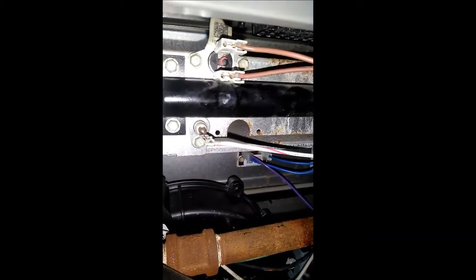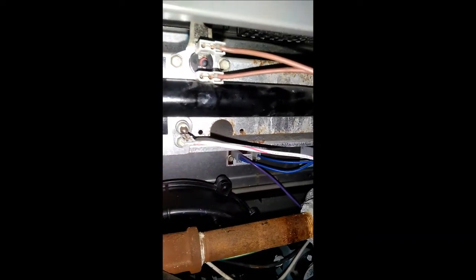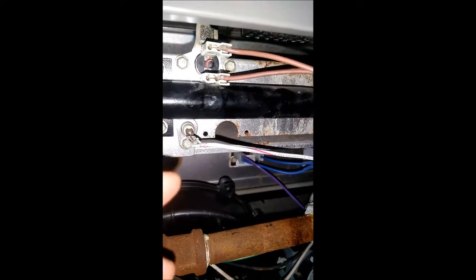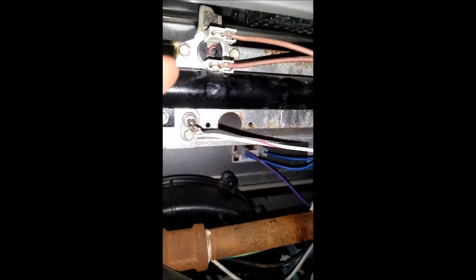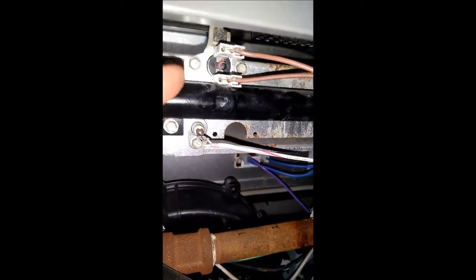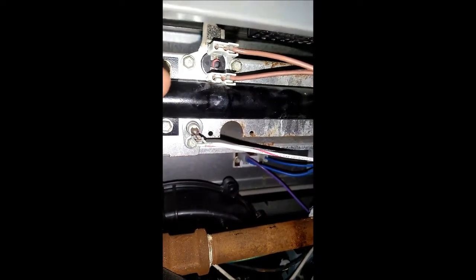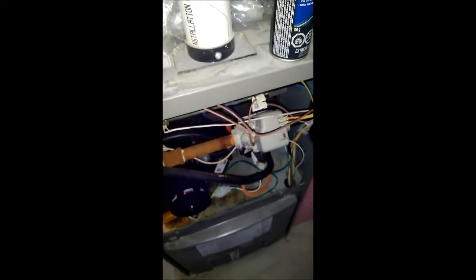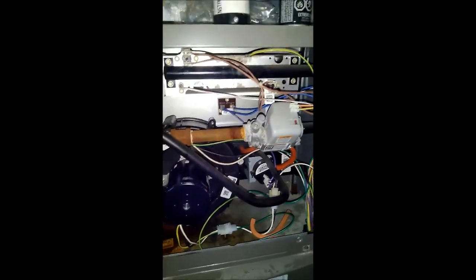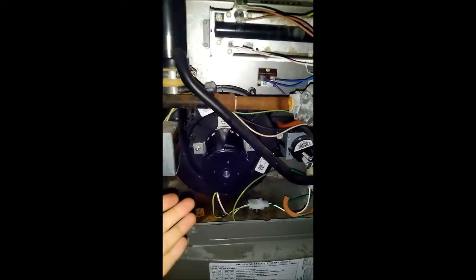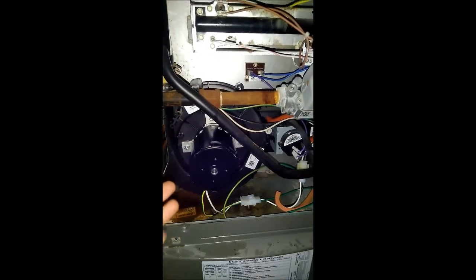So this really is just like the pressure switch. It works the same way. It's either infinite resistance or zero resistance, and flicking that switch back is like resetting a circuit breaker, and then it'll have zero resistance as long as there's no flame on the other side. So without further ado, I give you the completely fixed and normally functioning furnace with replacement inducer assembly and properly functioning rollout switches.